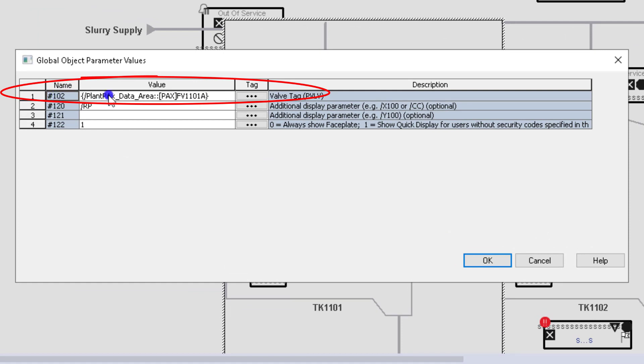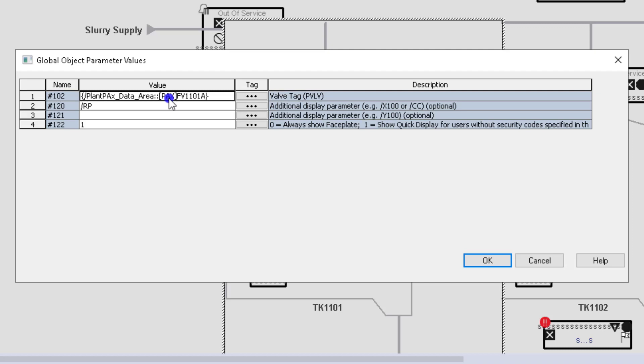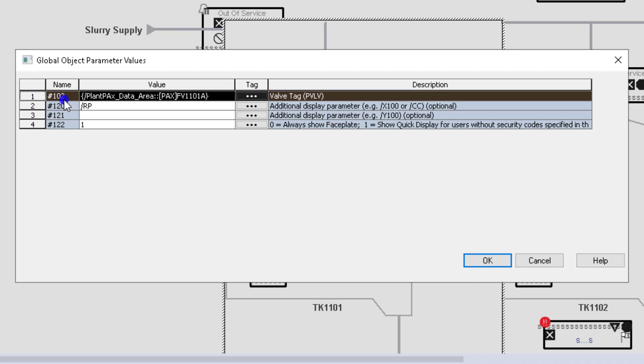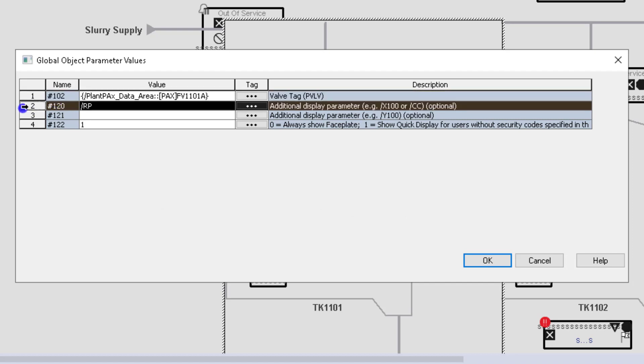It gives the actual shortcut, the PLC shortcut that we're currently using. So that's the HMI shortcut from the HMI, which would be the FactoryTalk Linx or RSLinx Enterprise. The shortcut you have set up there that is talking to the PLC file. We're talking to the PLC processor and then the tag name. So that's what they have in 102 right here.